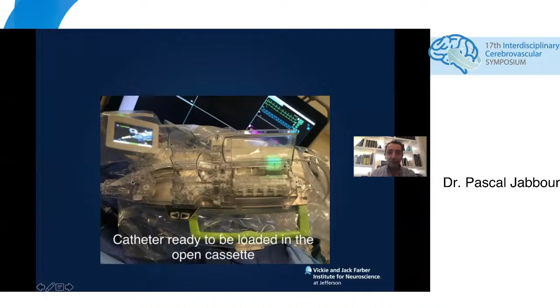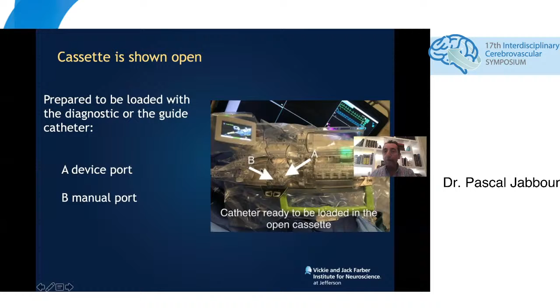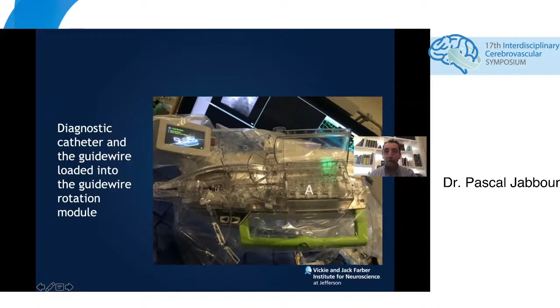Here, the catheter is ready to be loaded in this open cassette. I'll show you later on. And that's the device port in A. This is where your device port will go. And then the manual port: you always have a manual port where you place your wire that doesn't have to be manipulated during the procedure. Here you see that the diagnostic catheter is loaded. Here it is with the TUI. And as I said earlier, you have this small screen that will tell you each time what's the next step.